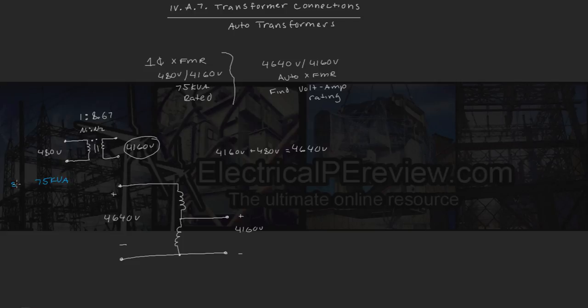Now if we take the maximum power that this single phase transformer we're working with is rated for, which is 75 kVA, we know this equals our complex power S, which is the same thing as volt times amps. So we can take this value, divide it by our voltage on each side, and that's going to find our primary current and our secondary current. So if we want to find IP, we divide 75 kVA by our primary voltage of 480, and we come up with a primary current of 156.25 amps. Likewise, for our secondary current, we divide our rated power of 75 kVA by our secondary voltage of 4160 volts, and we come up with a secondary current of 18.03.